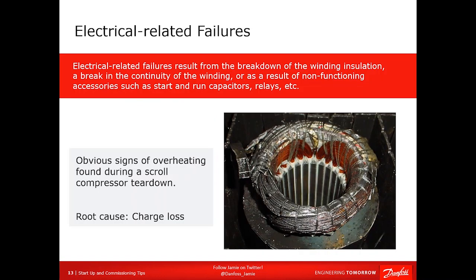So electrical related failures, how do they work? Well, there are some common ones, all right, but usually they show themselves as either a break in the winding or lack of motor cooling. A lot of times you'll get a non-functioning or dead start capacitor. Without the start capacitor, that unit is going to sit locked up, drawing about 6 times its normal current. In this case, we have an image of a failed one.